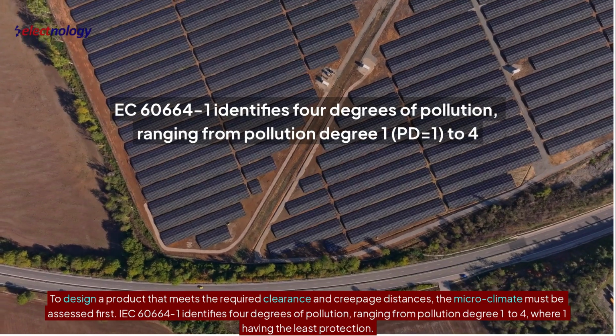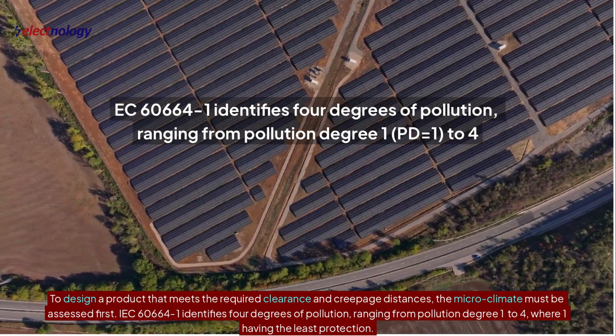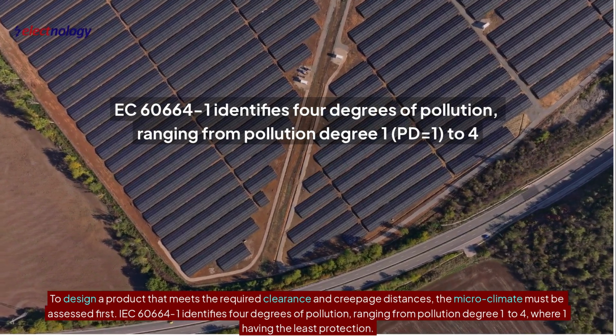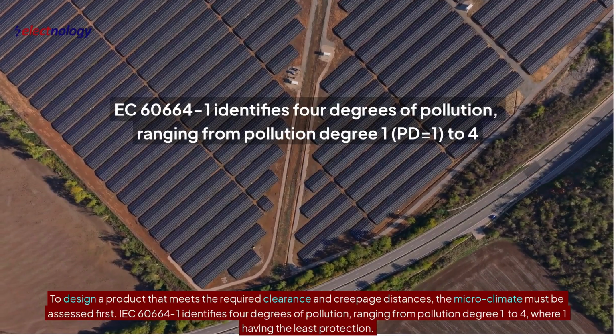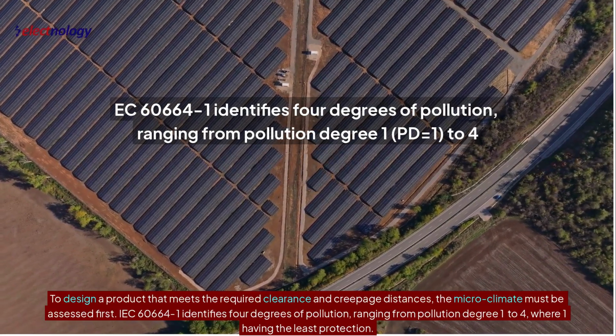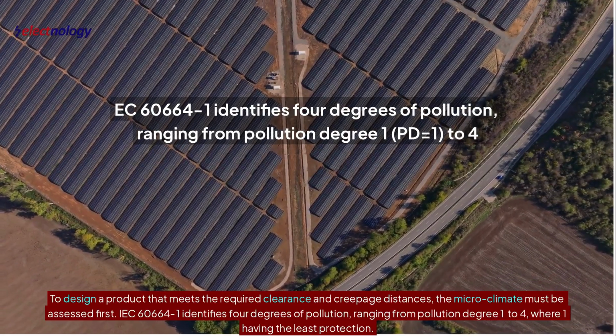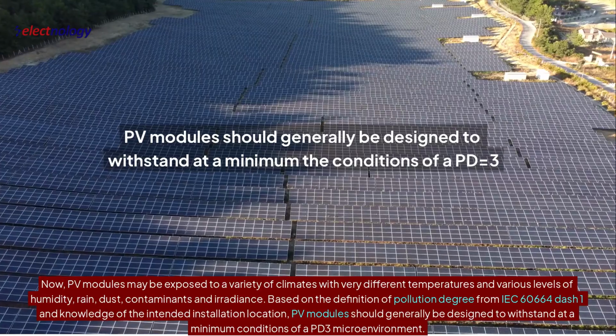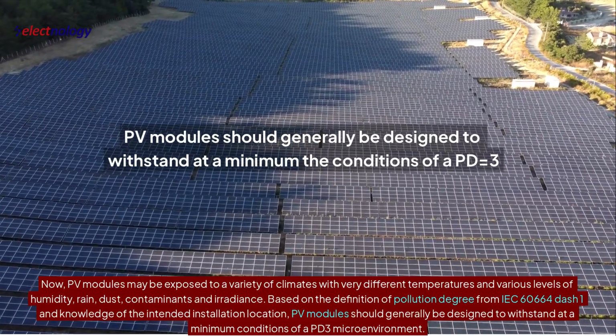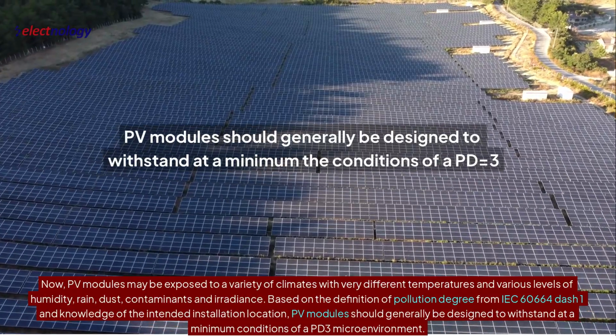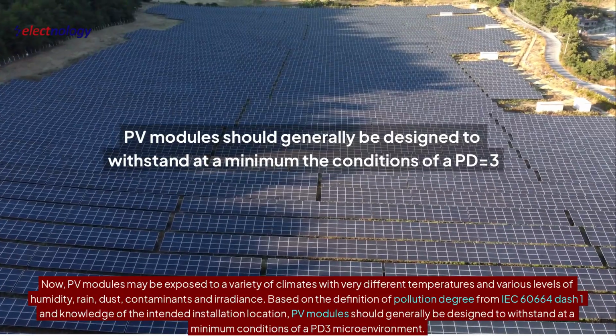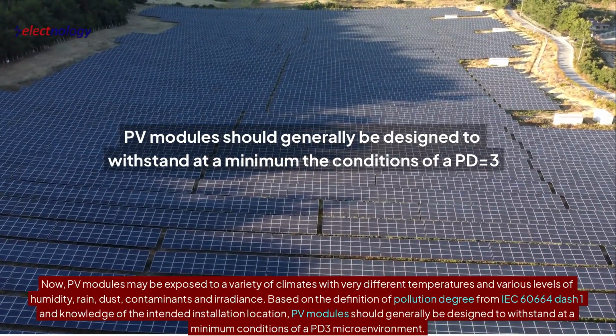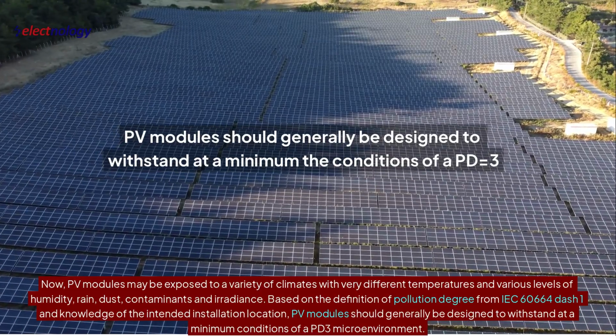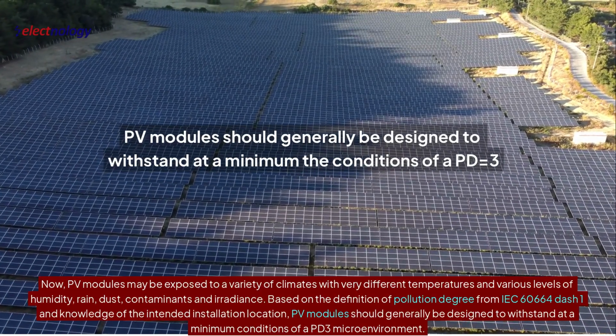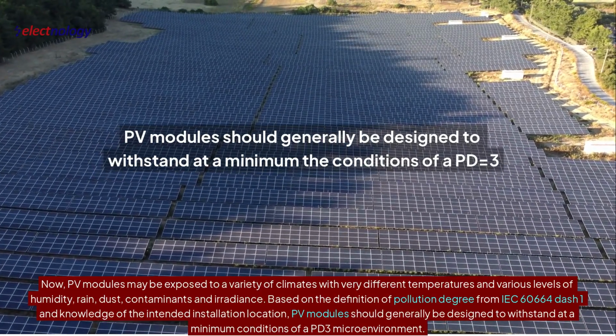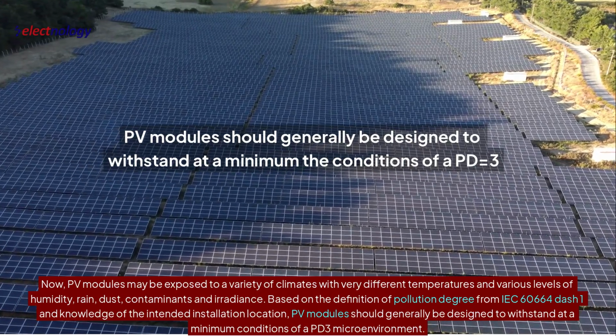To design a product that meets the required clearance and creepage distances, the microclimate must be assessed first. IEC 60664-1 identifies 4 degrees of pollution, ranging from pollution degree 1 to 4, where 1 has the least pollution. Now, PV modules may be exposed to a variety of climates with very different temperatures and various levels of humidity, rain, dust, contaminants, and irradiance. Based on the definition of pollution degree from IEC 60664-1 and knowledge of the intended installation location, PV modules should generally be designed to withstand at a minimum conditions of a PD3 microenvironment.